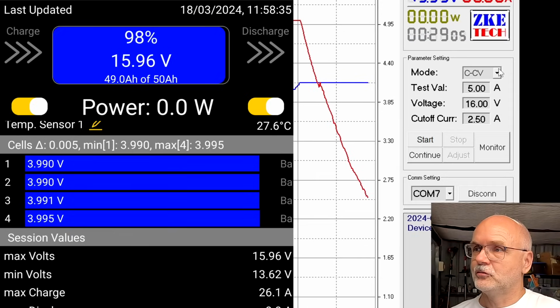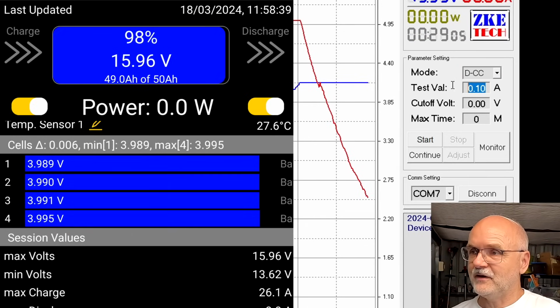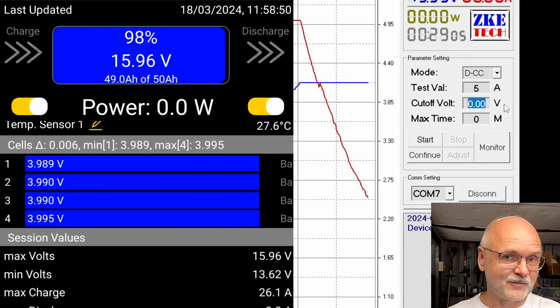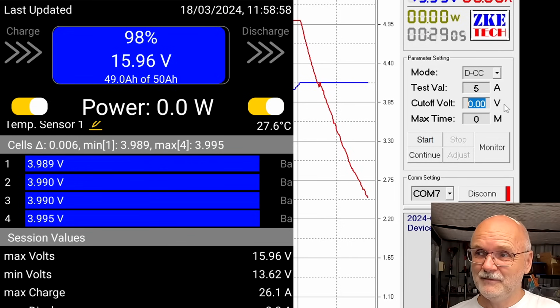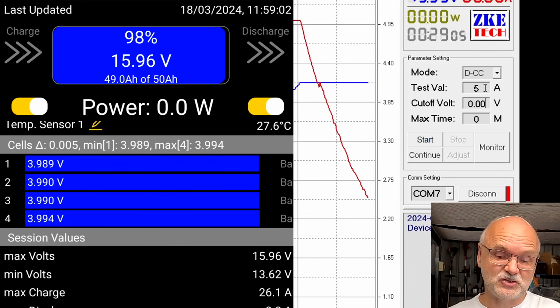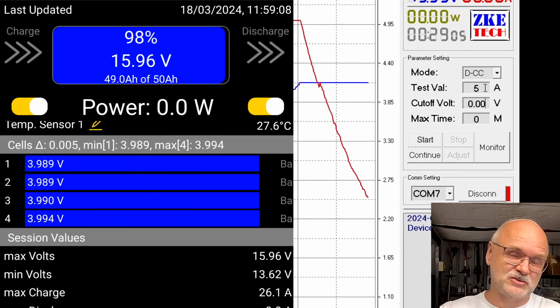We are now going to start our discharge test, which we'll do with only 5 amps, discharging down to 0 volts. This is because the EBC A20 tester can only do 86 to 89 watts of discharge power. Even if I set it to 20 amps, it will only discharge with 5.7 amps anyway, because that's the maximum power it can actually deliver.